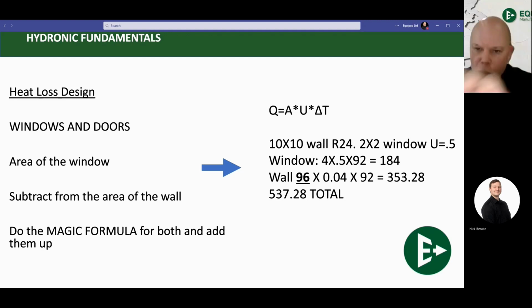So all we do is we remove the window from the wall and do its math first. We have a 2 by 2 window, 4 square feet. We have a U value of 0.5, and we have a temperature differential of 92 again, minus 22 Fahrenheit outside, 70 degrees inside. 4 times 0.5 times 92 is 184. So it's 184 BTUs leaving through that window. Our wall is now 96 square feet, so we have 96 times 0.04, because the R value did change in this calculation, times 92, our temperature differential from 70 to minus 22. And that math is 353.28.